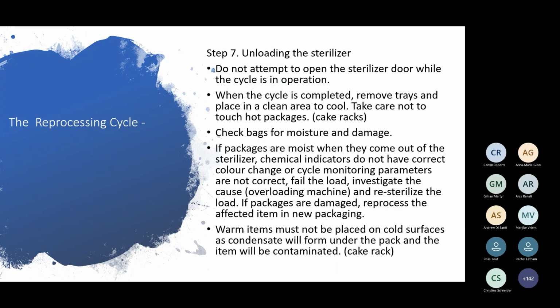After the cycle is finished, we're going to unload the sterilizer. Please don't try and open the door while the cycle is in operation, because you'll just damage the door or whatever, because you're not going to get it open. When the cycle is completed, make sure you remove the trays and place in a clean area to cool. Take care not to touch hot packs. So it's a good idea to take the trays out and put them on a cake rack or something like that. Please don't put hot instruments straight on a bench, because you will get condensation in the packs, and therefore your bags will be contaminated, because you'll get moisture permeating through the bags.